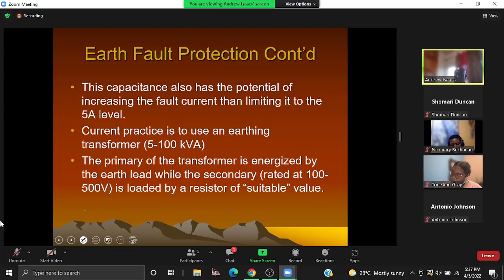Yeah, while the secondary, so the primary of that transformer is energized by the earth lead. So that earth lead that is coming from the generator. Yeah, we earth the generator at the star point. We have that earth. The fault current that flows through that earth lead will be the primary current for the earthing transformer.